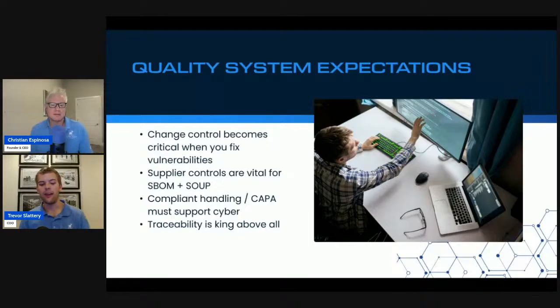Yeah, I think that's an excellent point. This isn't something that you can do just as you're designing the product. It needs to carry through all the way down. So even with vulnerabilities that you're identifying in the early stages of the product, they might have a little bit of a different process for identifying them later on. Some of the factors with even how they're identified can change. For example, one factor that can come up with post-market vulnerabilities that's not going to be present in pre-market vulnerabilities would be reporting confidence or exploit maturity, where you're understanding exactly how verifiable and how true is the information that you're getting in from a third-party resource, whereas during the pre-market phases, you're likely going to be collecting everything yourself. So it's a little bit of a different lens that we're looking at it, but it needs to carry through all the way down.